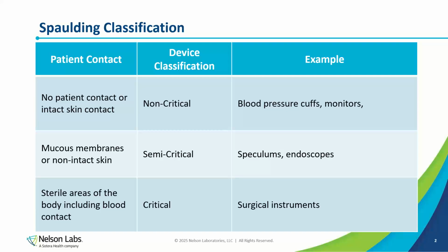And so while a high-level disinfection may be the most conservative choice for that part of the robotic device, it's not going to be feasible with the chemical disinfectants that are used for high-level disinfections. And it may not even be needed, because again, it's a non-patient contacting portion that in most cases is going to be covered with that sterile drape. And so really that intermediate level disinfection using that wipe is what I recommend, and I think an appropriate procedure to demonstrate that the device can be safely reprocessed between uses.